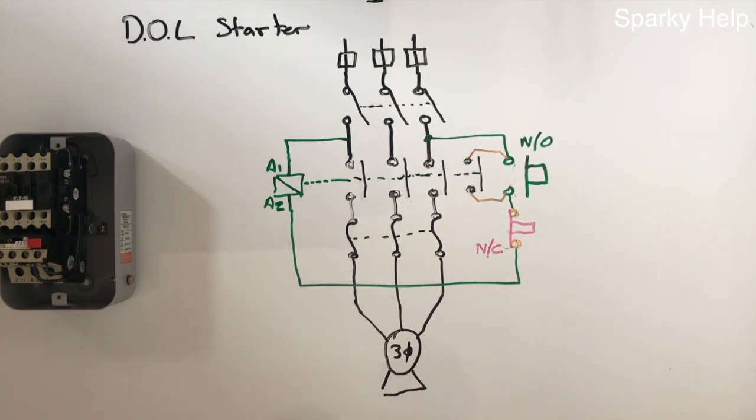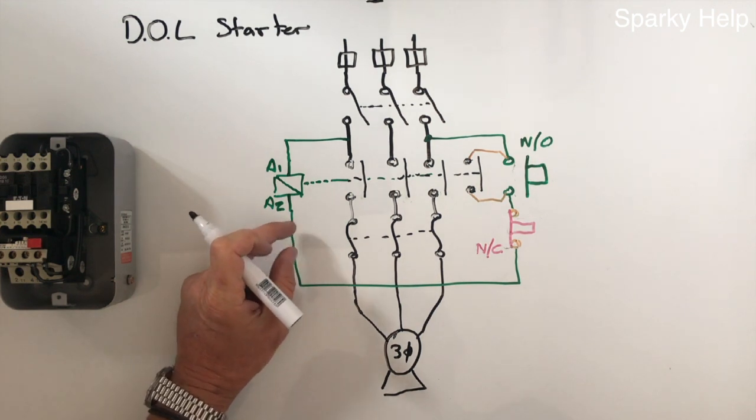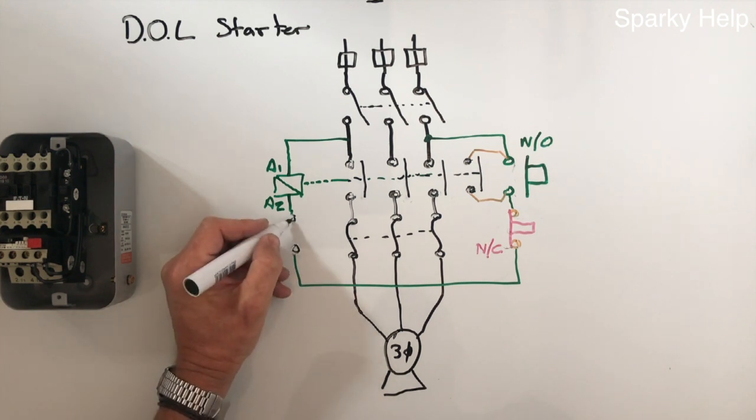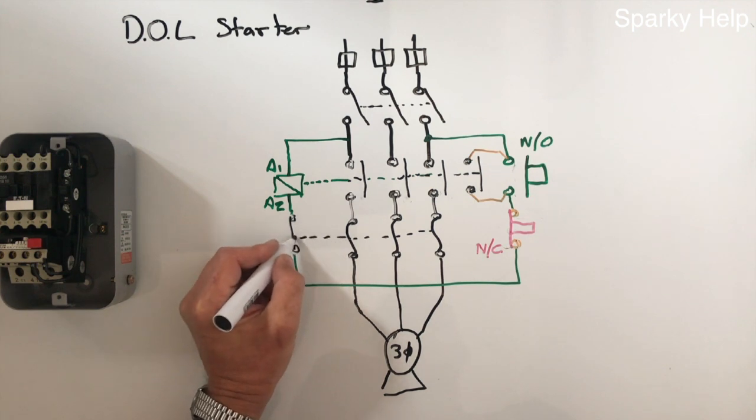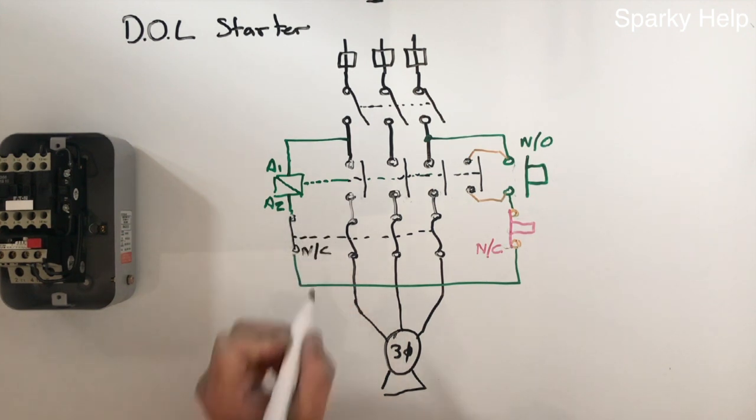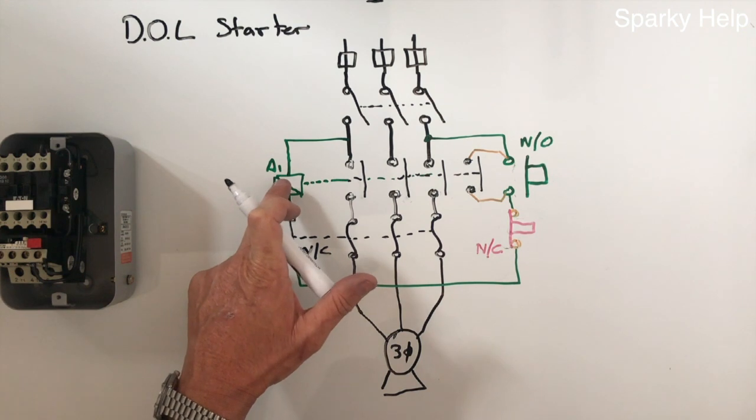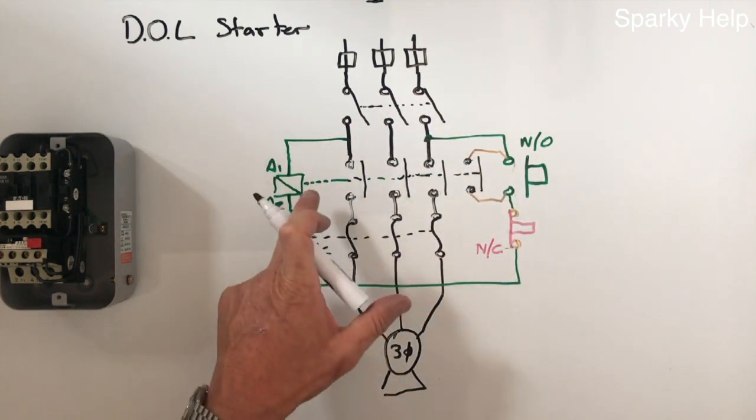So how does the overload work? Well the overloads are these things here. The overloads are bimetallic strips and when you pass current through a bimetallic strip, which are two dissimilar metals stuck together, one will expand more than the other. So when you pass current through them will warm them, depending on how they have been made, they will bend. And when they bend they will operate a switch. So the switch for that is internal within it, but it was fixed. It's basically here. And this is also a normally closed switch, so when the overloads overheat, they open this contact here again, breaking the contact, breaking the circuit around the start circuit and these contacts open.